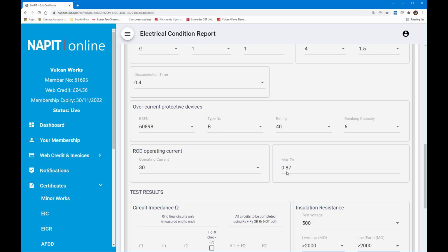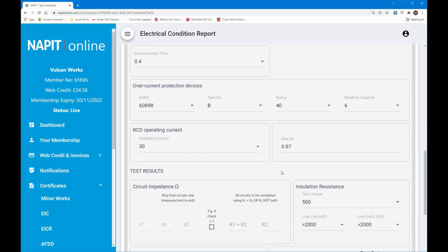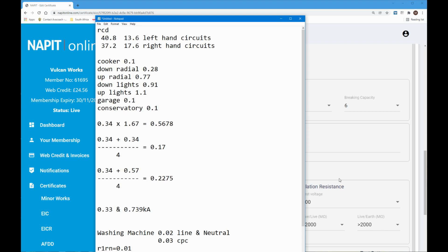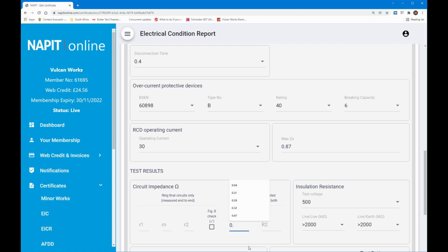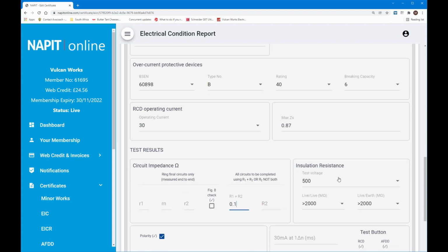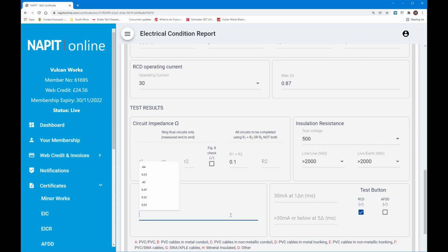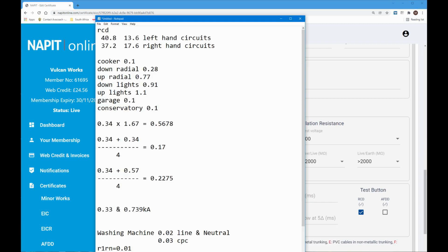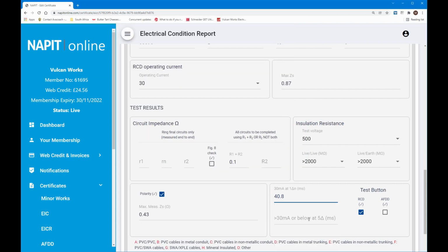That brings the ZS at 0.87. And the R1 R2 for that garage circuit is 0.1. That's from the EIC that I did. Again, we know that we did the insulation resistance for that. We did it as part of the garage installation. So the actual value here is 0.43. The RCD values are now on the left side. So these ones here. So it's 40.8 and 13.6. Okay, so that's that one done. So that's the garage circuit.